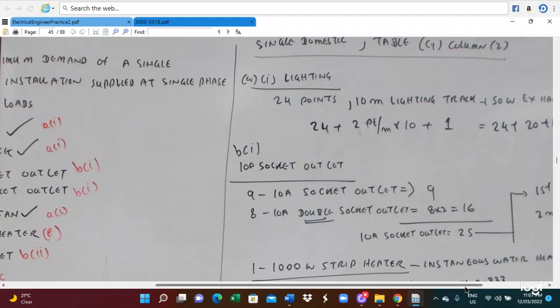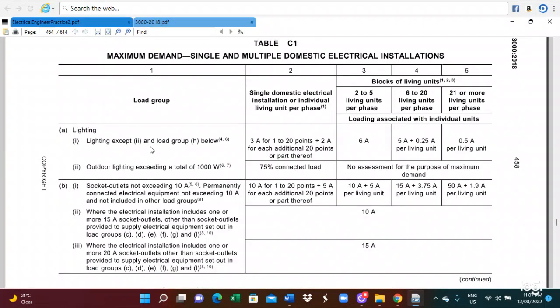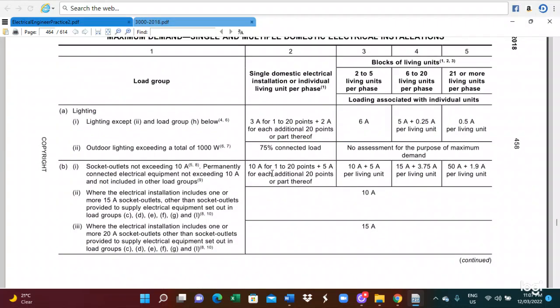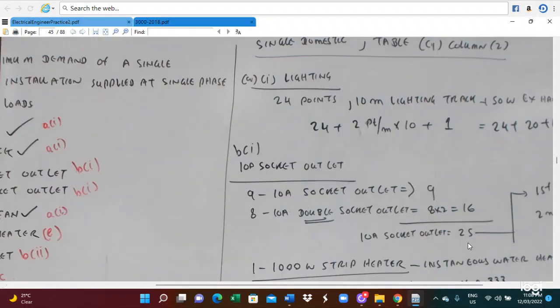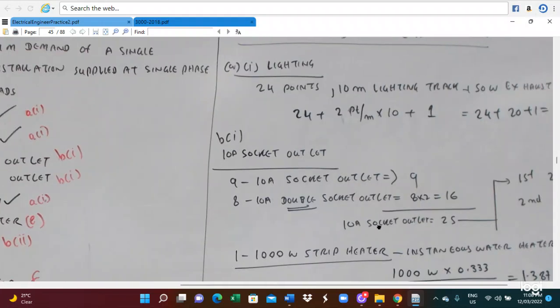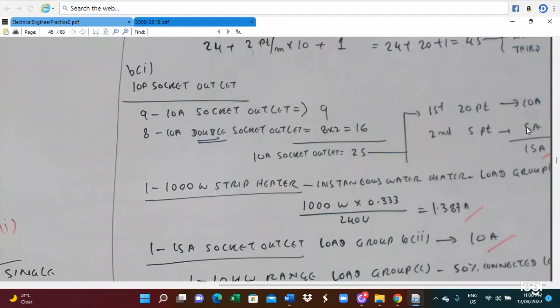So how do we calculate the socket outlet? Socket outlet is load group B(i). For the first 20 points we take 10 ampere, and for another additional 20 points we take 5 ampere. So this is load group B(i). Load group P1, this is the load group B(i) here. First 20 points, you take 10 ampere. Another additional 20 points, you take 5 ampere. Therefore, the total socket outlet is 25. So for the first 20 points, we take 10 ampere, and for the additional 5 points, we get 5 ampere. So there we get 15 ampere.